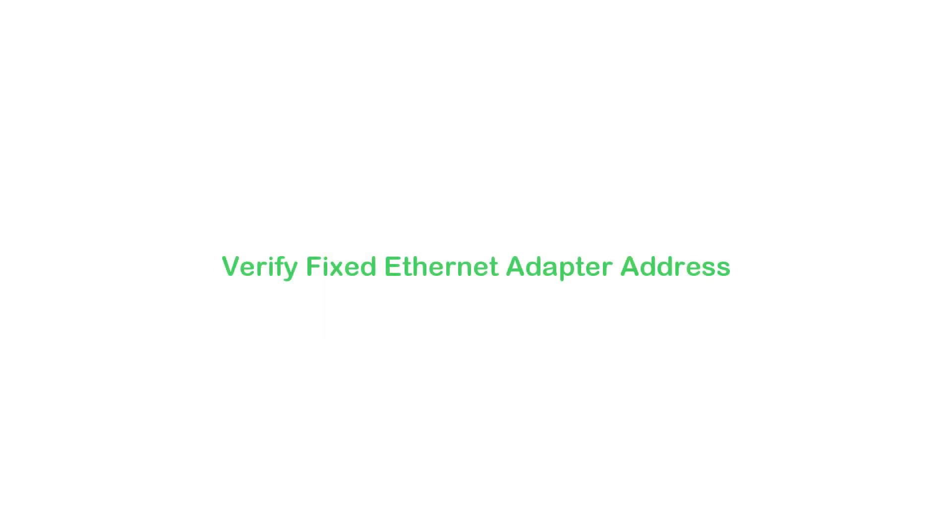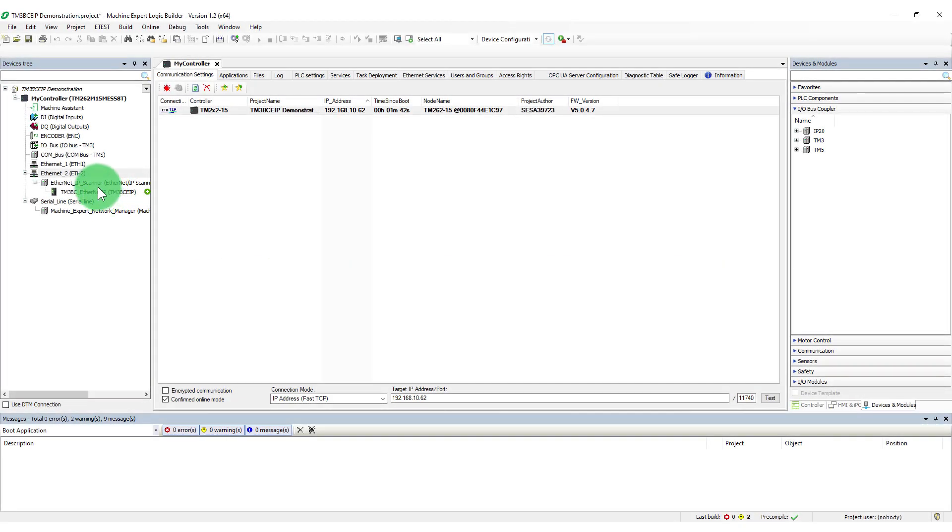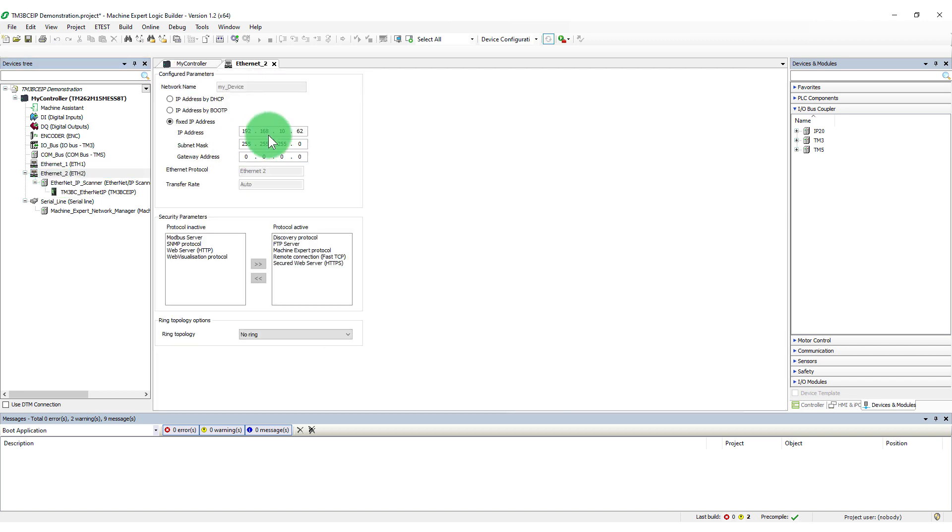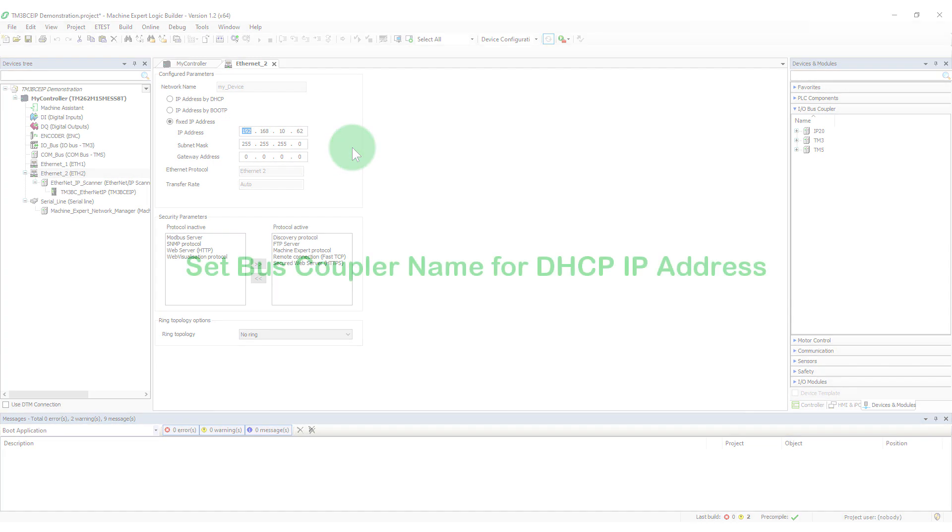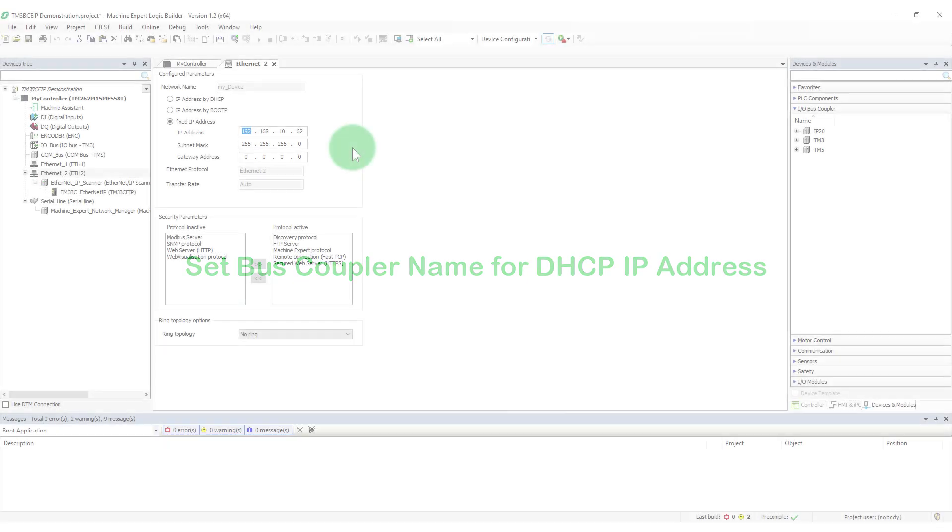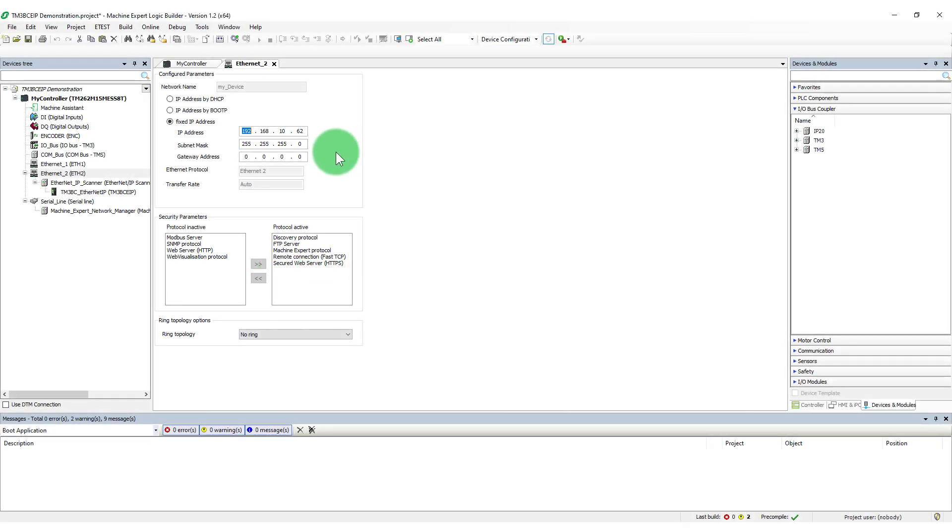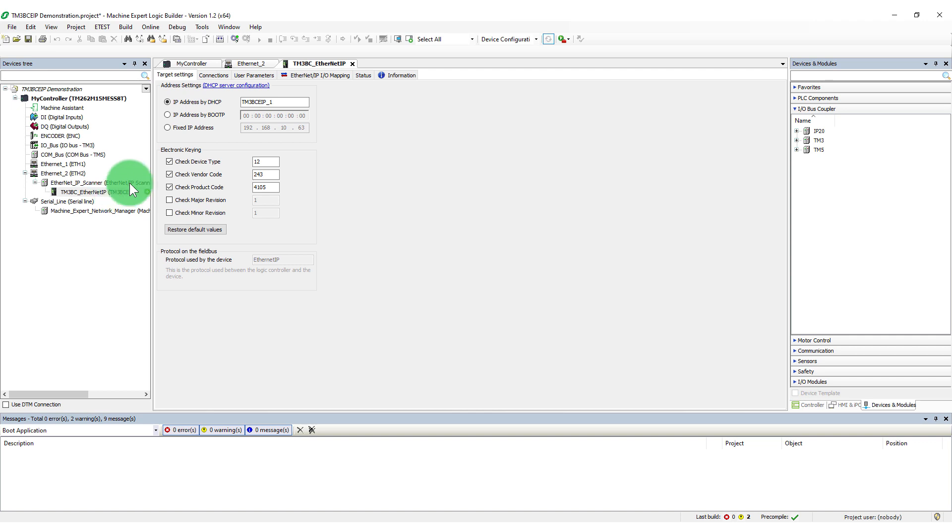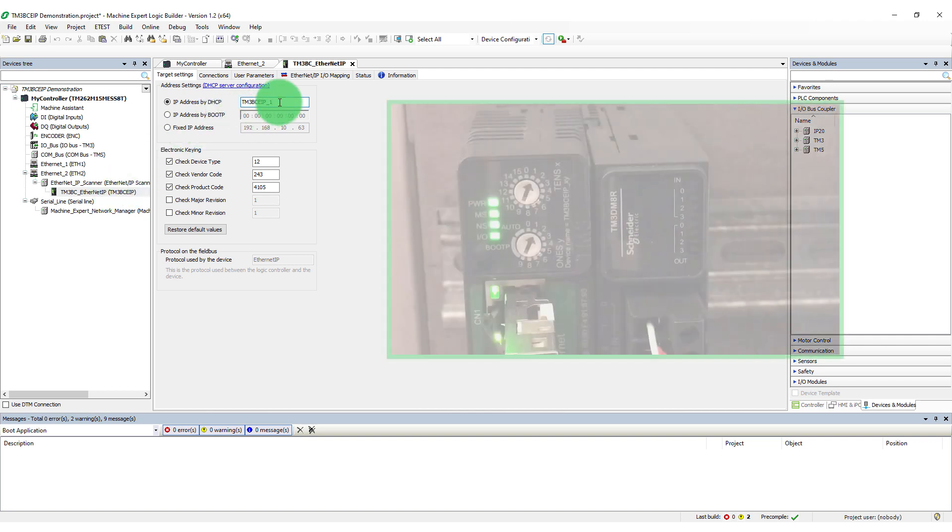This demonstrates using DHCP to address the bus coupler. The Ethernet adapter for the PLC must use a static IP address. Double-click on the bus coupler icon. In the Target Settings tab for the bus coupler, select IP address by DHCP.